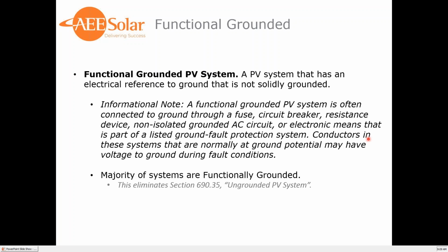So what this is saying is a functionally grounded PV system is a PV system that has an electrical reference to ground that is not solidly grounded. All of the inverters that we've been using for the last decade or so have fit this criteria. There's really no difference between the two, and since the majority of the systems are functionally grounded, this now eliminates section 690.35 ungrounded PV systems from the code.